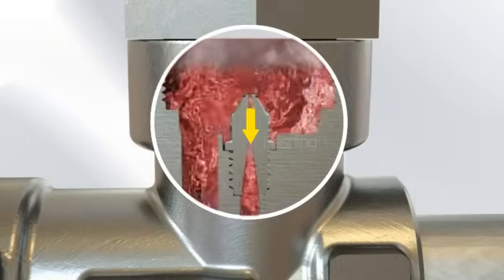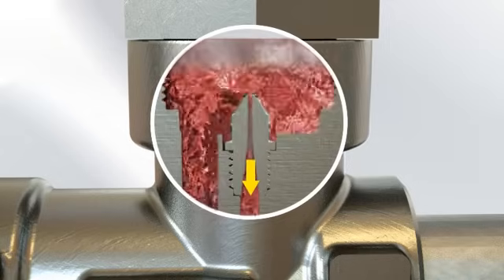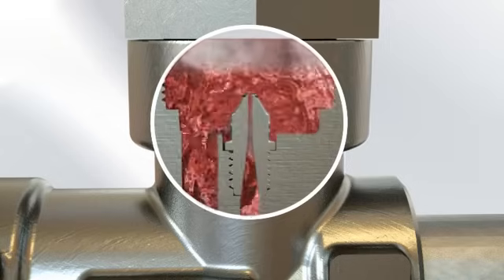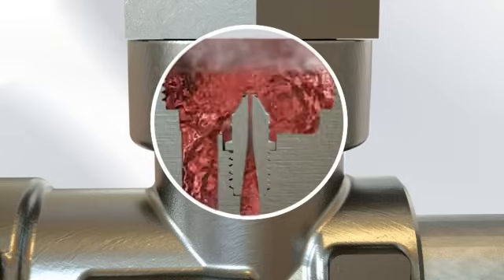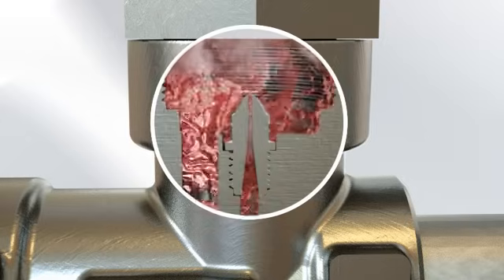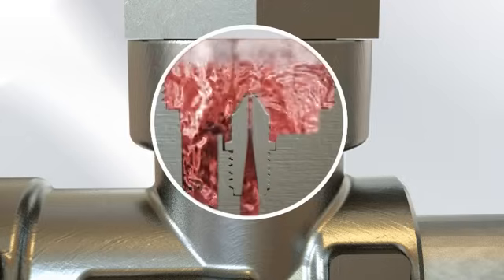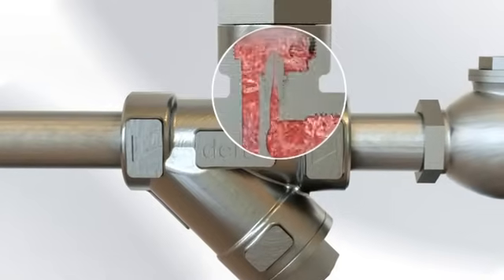This flashing creates a back pressure zone in the mouth of the Venturi. Because condensate is 1,000 times denser than steam, it is able to push through this back pressure zone while restricting the steam.